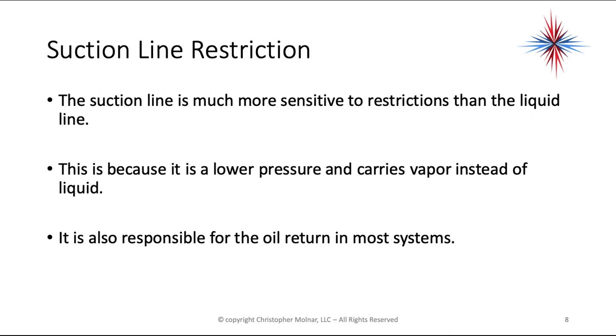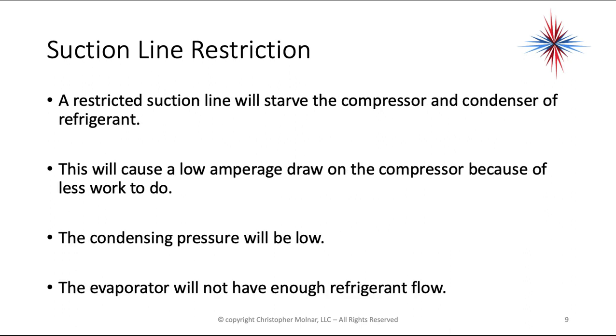On the opposite side of the system, the suction line is much more sensitive to restrictions than the liquid line, because it operates at lower pressure and carries vapor instead of liquid. It's also critical because the suction line is responsible for oil return to the compressor in most systems. A restricted suction line will starve the compressor and condenser of refrigerant, causing a low amp draw on the compressor due to having less work to do. The condensing pressures will also be low.